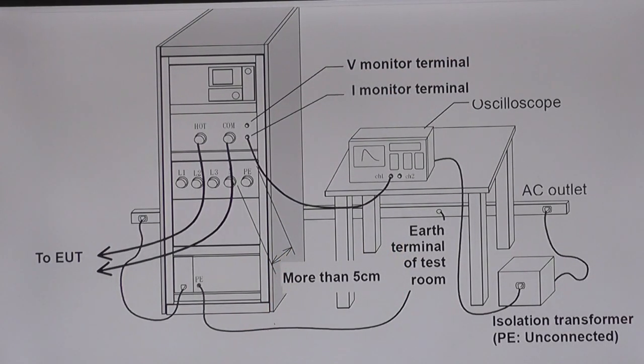There are 4 things I would like to highlight when connecting the equipment for the pre-check before the test. First, the lightning surge simulator shall be securely connected to the protective earth grounding using a 3-core AC cable with a grounding terminal. If the earth ground is not certain, connect the PE terminal of the surge simulator and the grounding terminal of the test room with the PE cable.